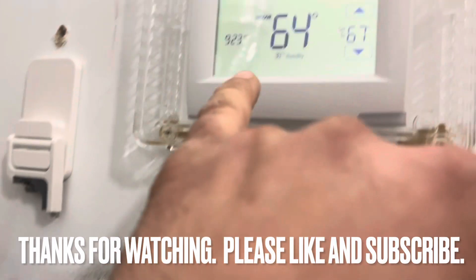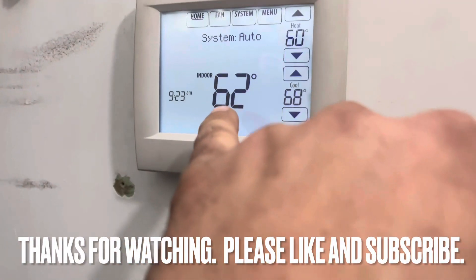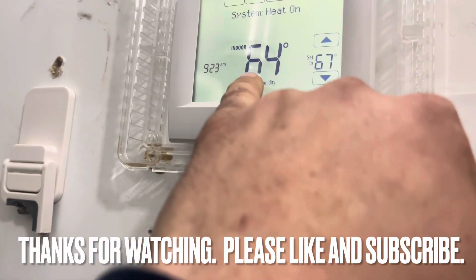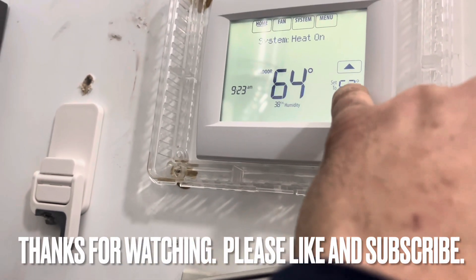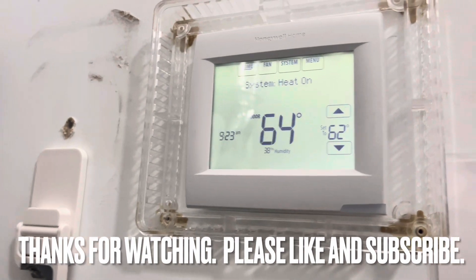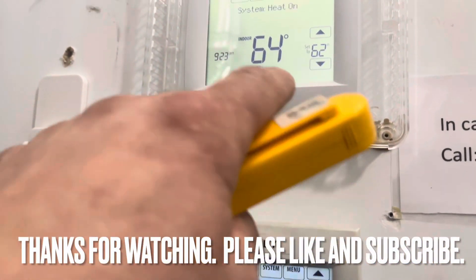So you can see right now this room indoor is 62. This sensor is in another room which I can't show you because it's in a lobby. And then this is the gym that we just hooked up — it's 64 in there. So we're going to bring this down to where they want it at 62, but the temperature is controlling. You can see how they're different — the temperature out there is being controlled by the wireless device.